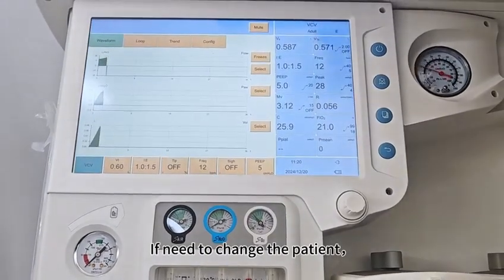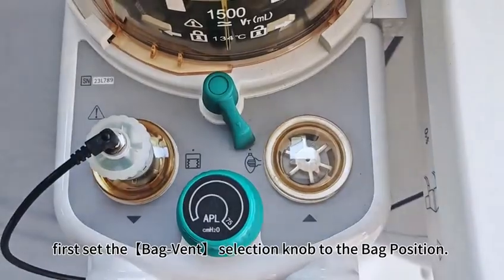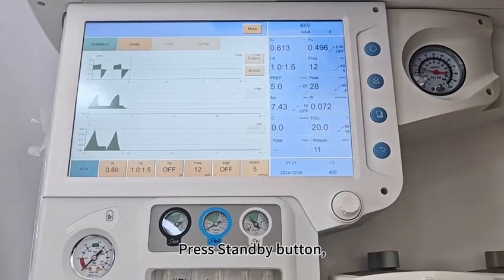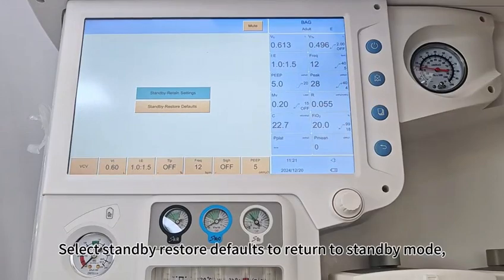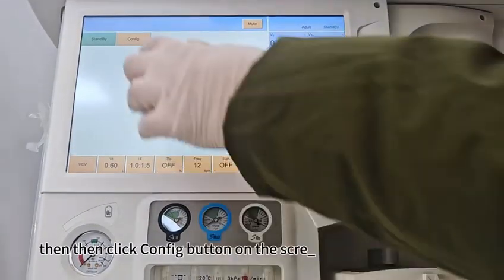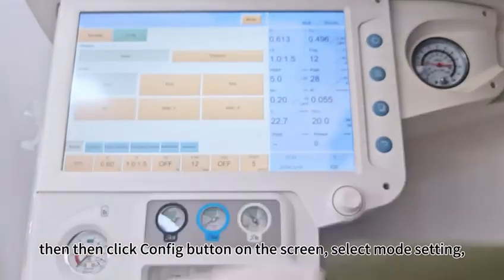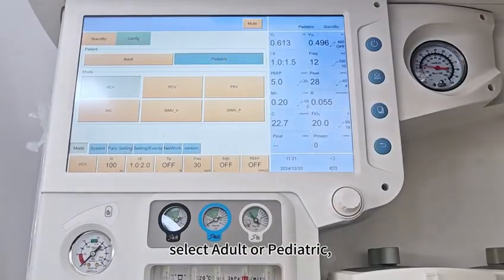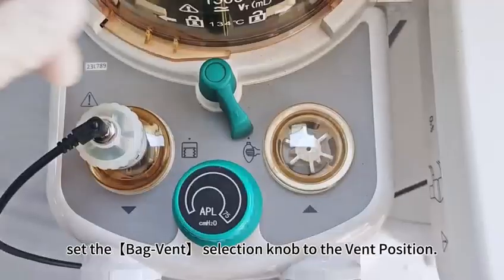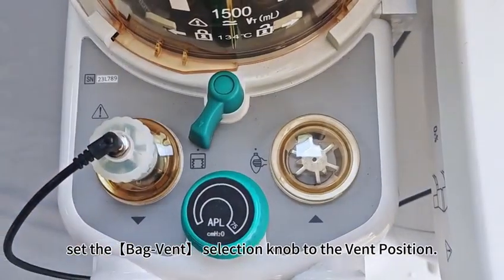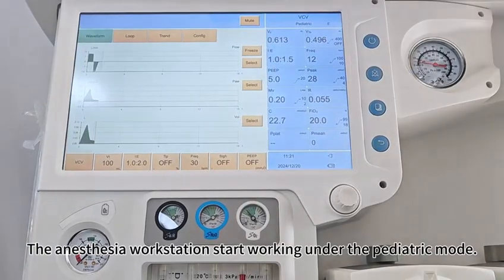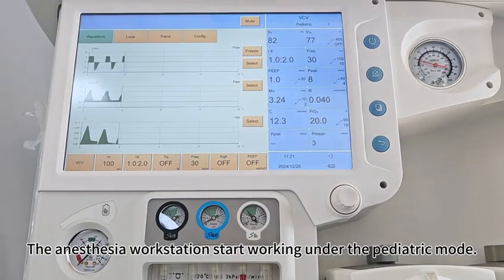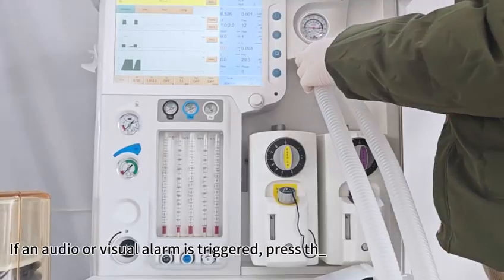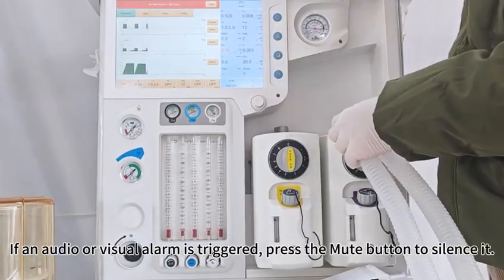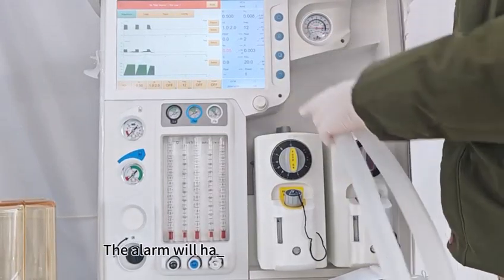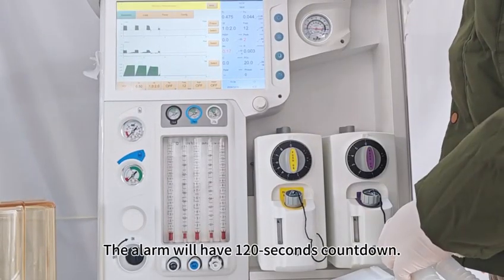If you need to change the patient, first set the bag vent selection knob to the bag position. Press the standby button, select standby, restore defaults to return to standby mode, then click the config button on the screen, select mode setting, and select adult or pediatric. Set the bag vent selection knob to the vent position. The anesthesia workstation starts working under the pediatric mode. If an audio or visual alarm is triggered, press the mute button to silence it. The alarm will have a 120 second countdown.